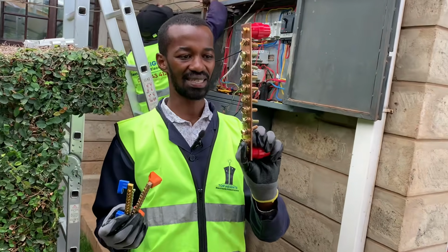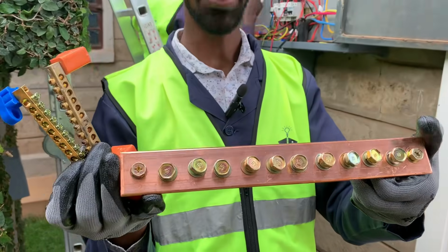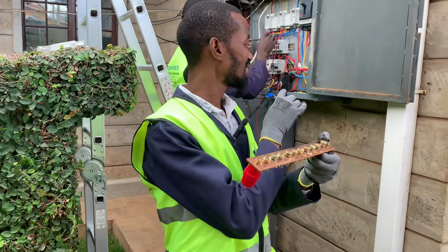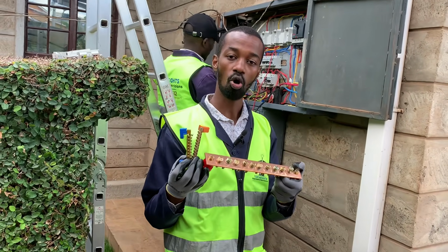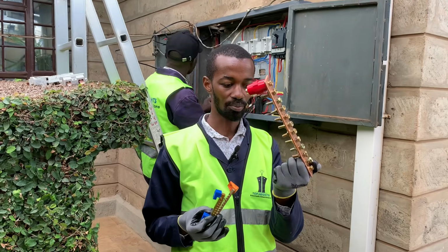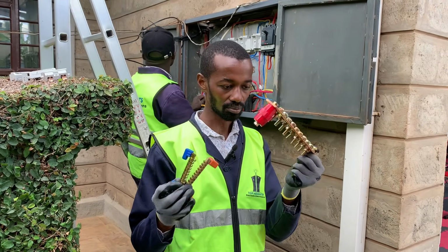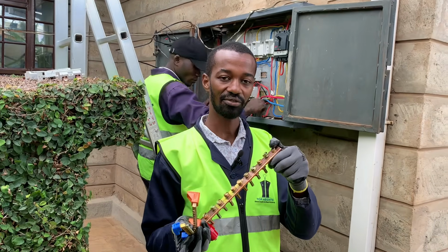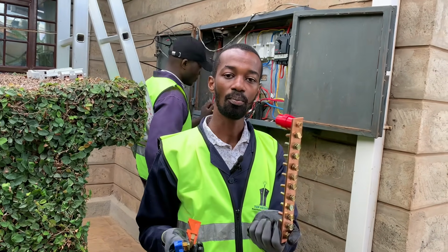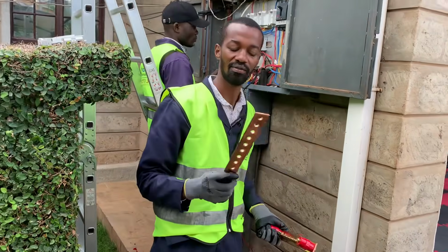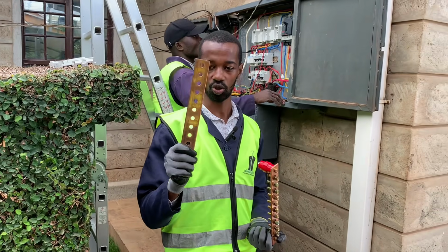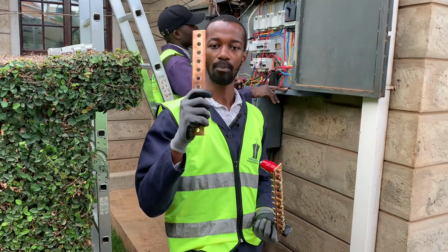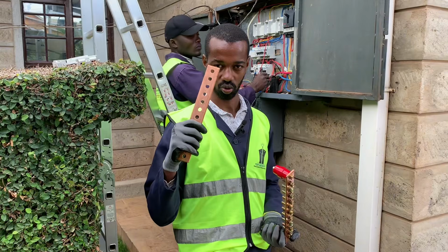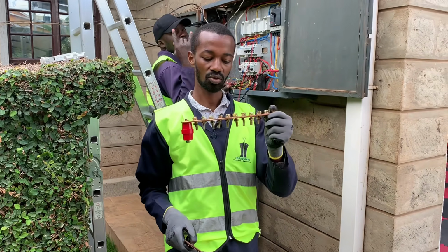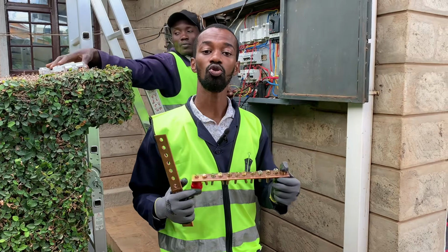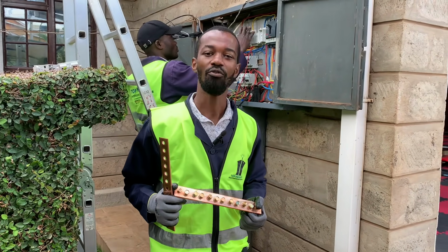Now, these ones are used in the consumer unit. But I have these bars here. This is a neutral bus bar. We'll be fitting it in this board, this termination board or distribution board. Why is this important and why is it different from this? As you can see, it is larger, with a larger surface area to hold the cable lugs properly. I also have another one here. We'll be connecting it to the earth connection. So this will be a point of reference for all the terminations before it goes to the ground. This one will be a point of reference for the terminations before it goes to the neutral, the return path for electricity.